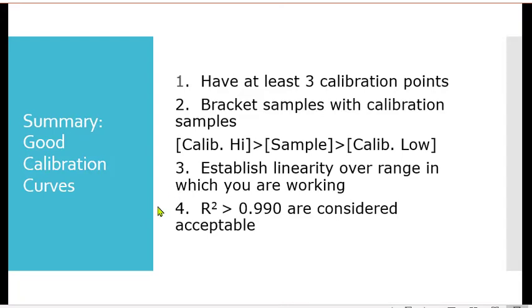So that is the point. Here's the summary that I would say. You need at least three calibration curves for anything you're doing in the academic labs. And if you're working out of academics, then you're going to want to do, as you go on and do more research, at least five calibration points. You need to bracket samples between your high and low calibration points. You want to establish linearity over the range in which you are working. And just to kind of put this at ease, if you're doing acceptable research work, an R squared greater than 0.990 would be considered acceptable.